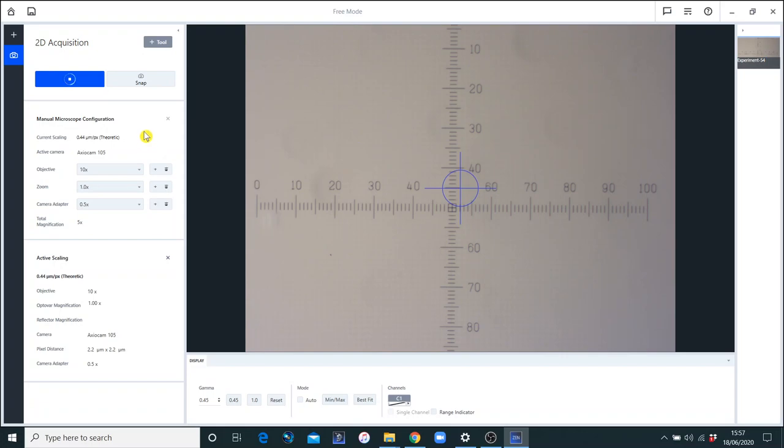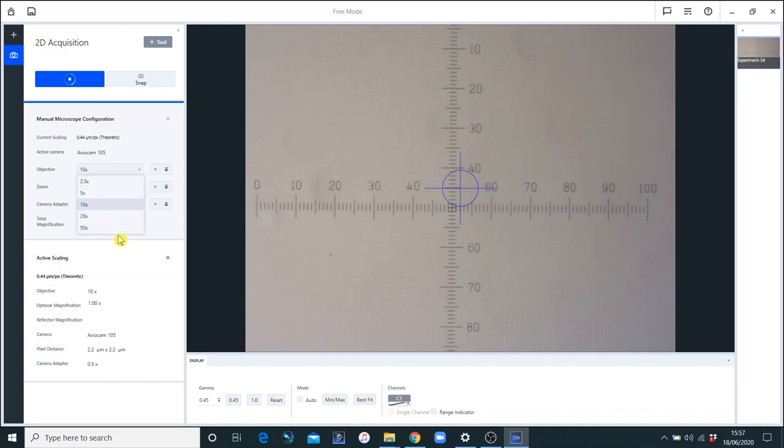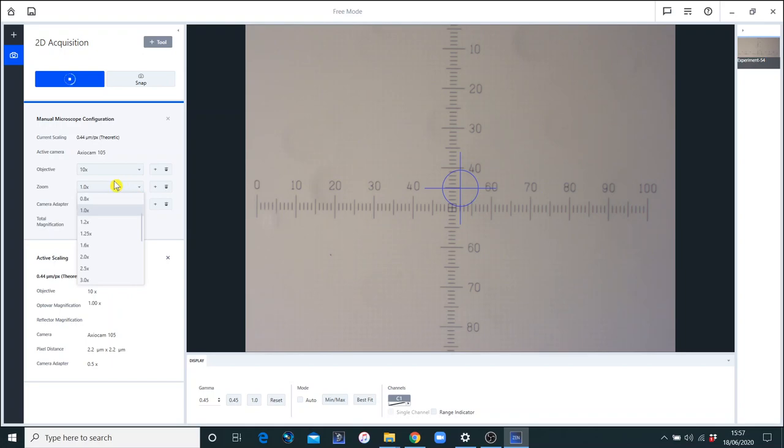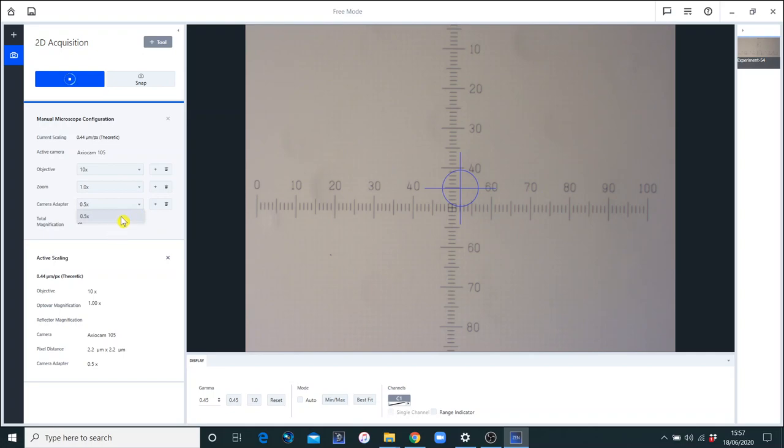Now when you get this out of the box, so to speak, you need to define this data set, this list of objectives, and this is going to match what you're using on your microscope. It'll come with lots of choices and you just basically delete the ones that you don't need until it matches your microscope configuration. Zoom - this is here for people who are using stereos. In a compound microscope, we're going to use it with a zoom of one, and we're just going to use that and nothing else. The C-mount adapter needs to be defined as well. In this case, it's a 0.5.